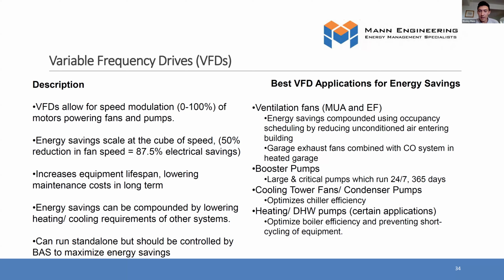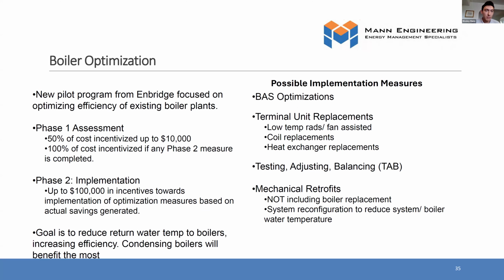Cooling tower fans and condenser pumps. Again, not only does this have savings on the fan and the pumps themselves, but it can actually optimize the efficiency of the chiller. So you're getting kind of compounding savings there. And heating and domestic hot water pumps, a similar example to the chillers, where not only are you saving on the pumps itself, but also you can optimize your boiler system.